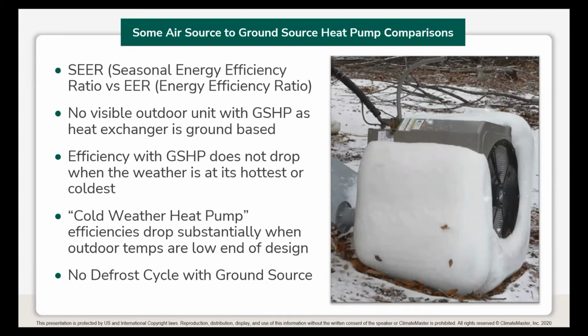Some additional differences. Our product, our ground source heat pump, is rated with an energy efficiency ratio, or EER, as opposed to what most homeowners are comfortable with, a SEER rating. We don't have a seasonal energy efficiency rating because of our relatively constant ground temperature. Our outdoor air going up and down in temperature has no bearing on our energy rating because we're using the ground. We have no visible outdoor unit. It's buried in the yard. And the efficiency, again, doesn't drop when the weather is at its hottest or its coldest.